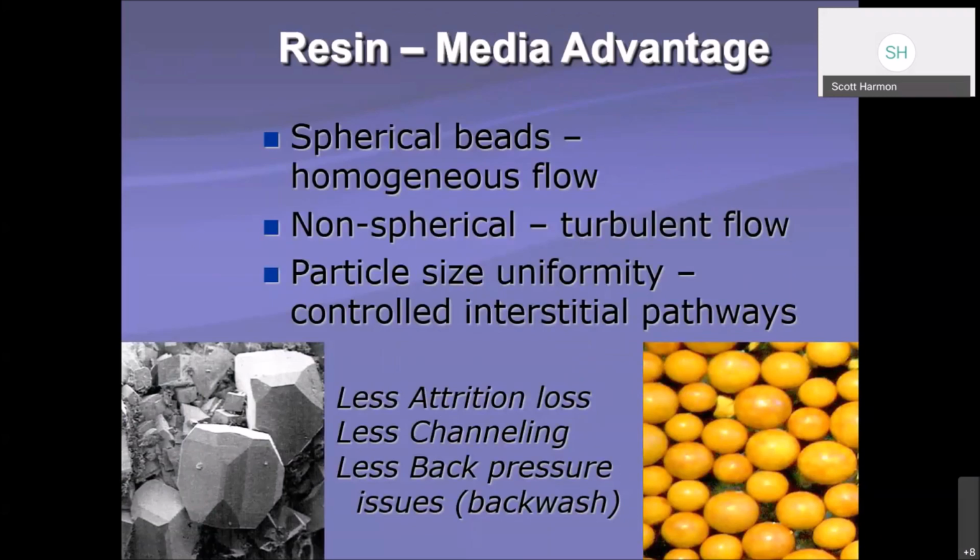All right, the next one is the resin medias. These are a different type of media, coated media, that can be used for arsenic removal. Spherical beads have a homogeneous flow, which means the annular spaces between the beads are going to be consistent, unlike standard sand filter media, where the sand grains are of different shapes and different sizes. With these spherical beads, the annular spaces between them are almost identical, which could be important in the removal.